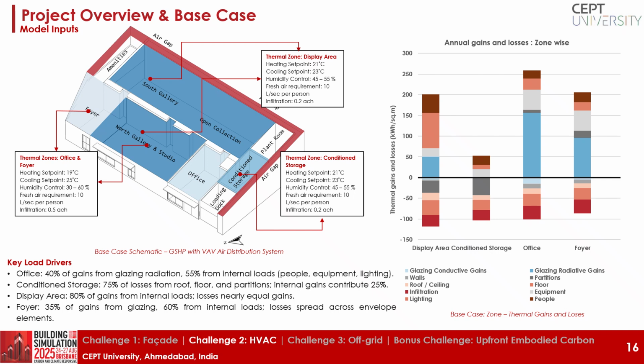Being a below grade building, the gallery contains critical spaces like display areas and condition storage where precise temperature and humidity controls are vital. The base case was modeled from the existing gallery's HVAC system, while the design case was refined through energy modeling. Our analysis on the annual thermal gains and losses of the base case showed that the gallery is made up of very different thermal zones, each requiring specific strategies.